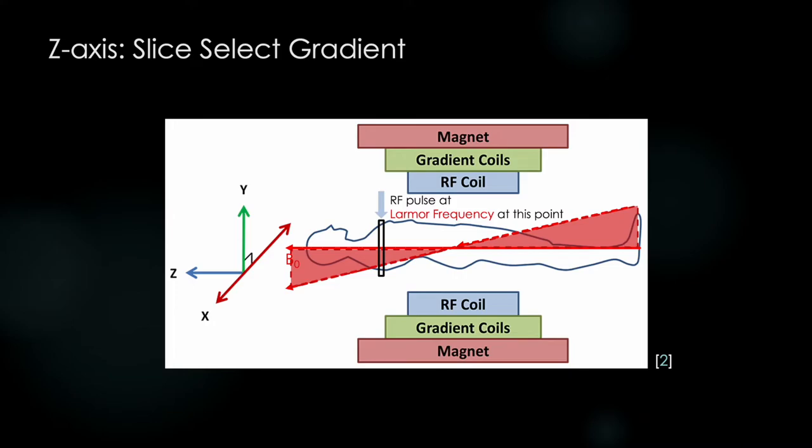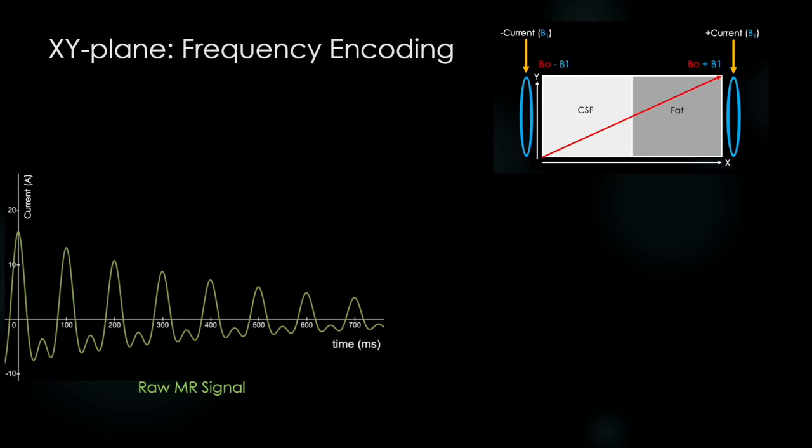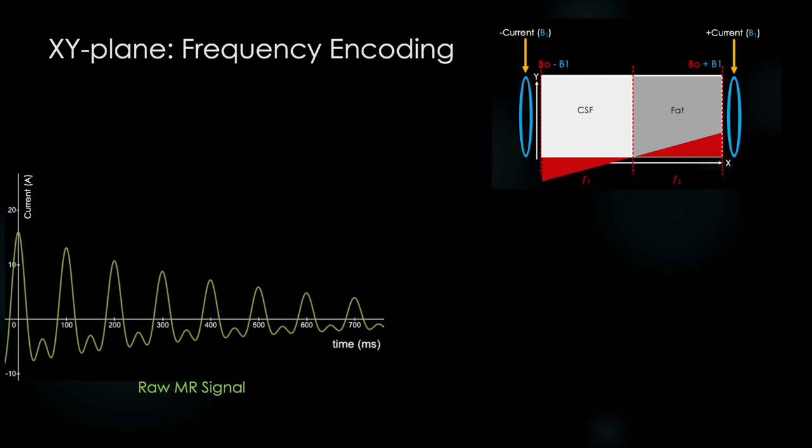The protons in our slice are already spinning, generating signal in our receiver coils, so we don't need another RF pulse. What happens if we simply turn these magnets on after slice selection and look at the signal? We get a much more complex looking signal now, and why is that?